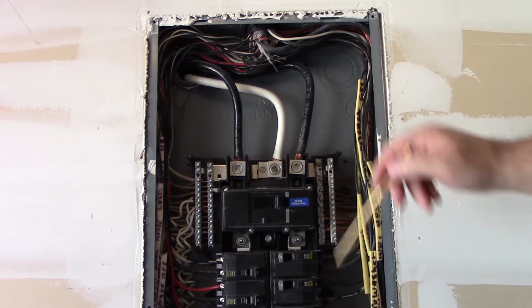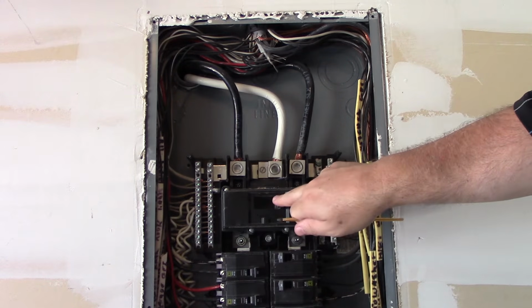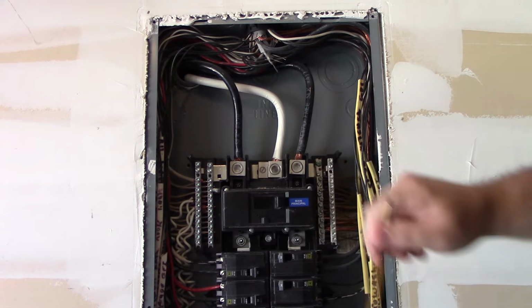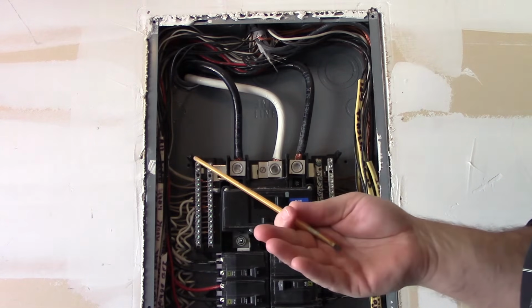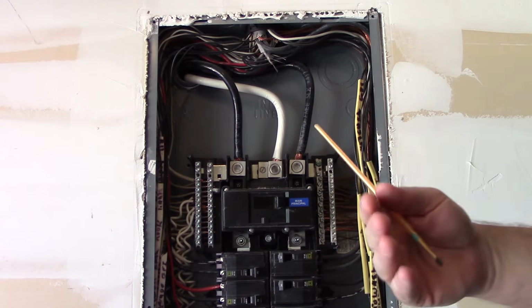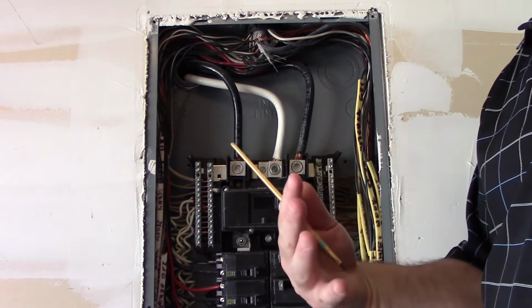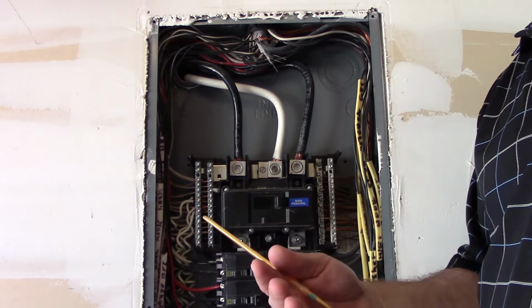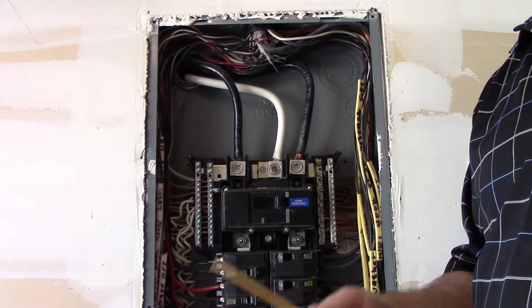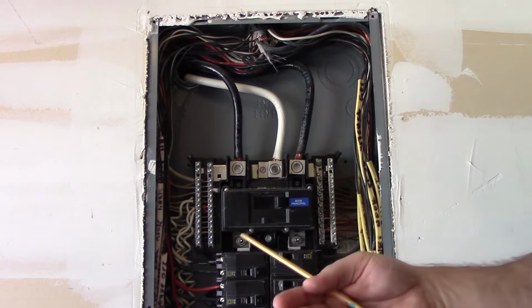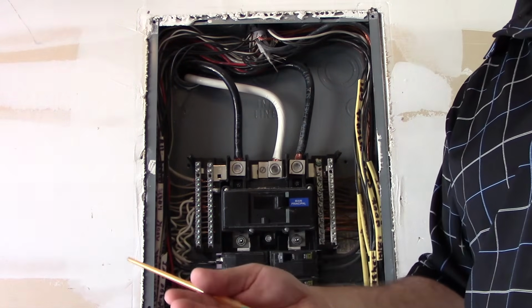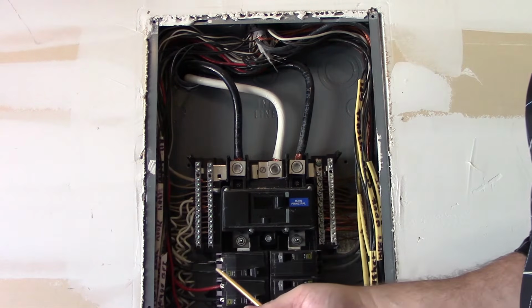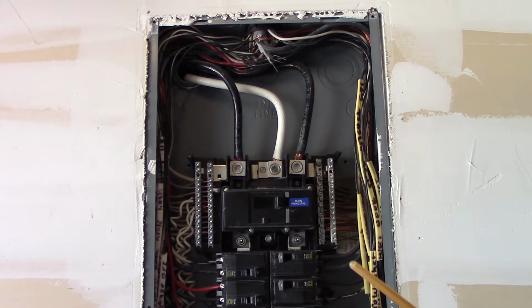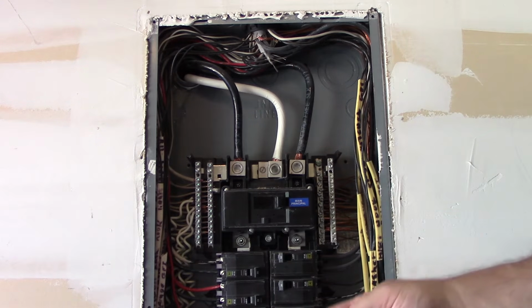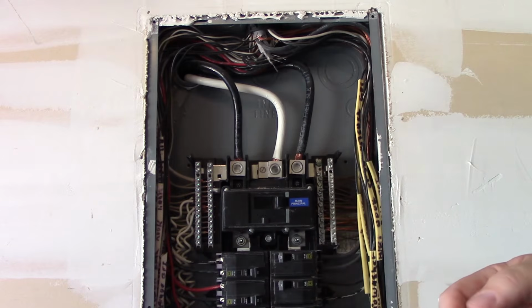And so I'm looking at it here, and here's our main breaker, again, off and on. It's in the on position. Now, again, if I'm doing an inspection, if it's a home inspector, I have to do an inspection on all the breakers that are on. I'm not going to turn any that are off on because they're obviously off for a reason. So I'm going to denote the fact that it's off and that I couldn't test that circuit. And if the legend matches up to it, then I'm able to point out which one it is. Obviously, it'll be clear because it's off, but you want to note that in your inspection report.